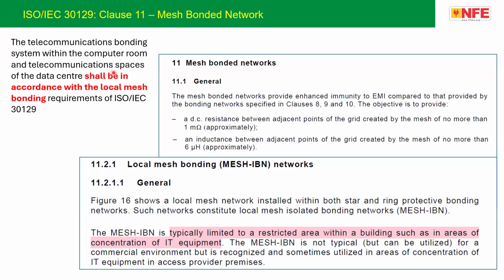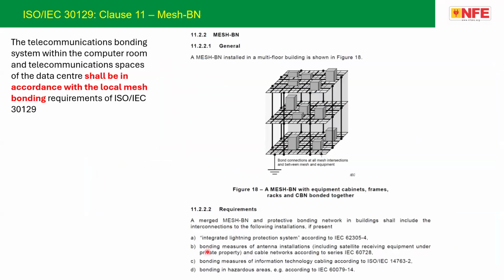Why I am showing this is, you look at the left side where I am moving the cursor, the 22237 says the minimum requirement of telecommunication bonding shall be in accordance with local mesh bonding. So local mesh bonding, called mesh IBN, is typically limited to a restricted area within a building, such as areas of concentration of IT equipment. That means it's for a smaller building, a smaller room with data centers, whereas for a larger building, what is required is mesh BN.